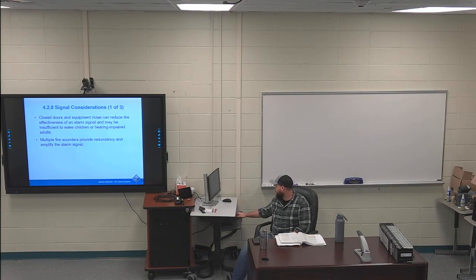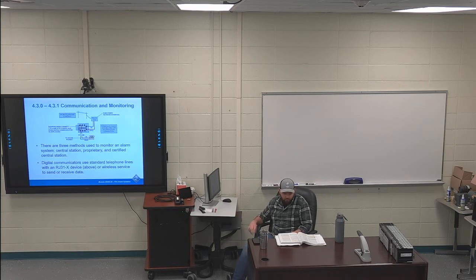Page 33, 430. Communication and monitoring. Monitoring options, 431. There are several options for monitoring signals of an alarm system. They include the following. I've got the certified central station bullet point, the first sentence of that highlighted. These are monitoring facilities that are constructed and operated according to a standard, and they are inspected by a listing agency to verify compliance. So these are just stations that are verified monitoring facilities.